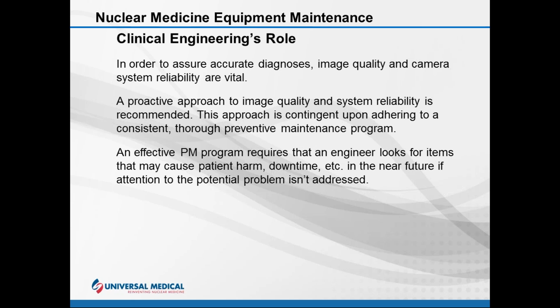Also in your roles, the patient safety devices are really highly important. Collision sensors, the e-stops that help to stop the camera in case of an emergency, and the collision sensors that, if the camera gets too close to the patient and starts to press on the patient, will stop the camera from moving. Making sure that these are functioning is vitally important.